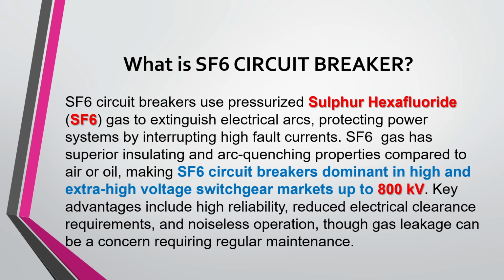Friends, SF6 circuit breakers use pressurized sulfur hexafluoride, that is SF6 gas, to extinguish electrical arcs, protecting the power system by interrupting high fault currents. SF6 gas has superior insulating and arc quenching properties compared to air or oil. This makes SF6 circuit breakers dominant in the high and extra high voltage switchgear market up to 800 kilovolts. So key advantages include its high reliability, a reduced electrical clearance required, and noiseless operation. Though gas leakage can be a concern requiring regular maintenance. So this is the only disadvantage or the problem it has, but it's a big problem to maintain the pressure inside the SF6 circuit breakers.